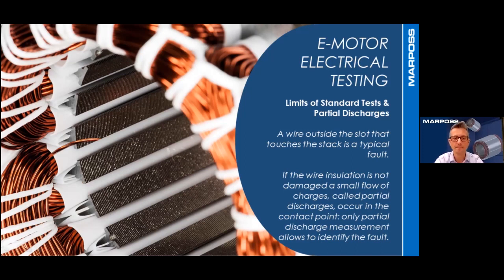In other words, the partial discharge measurement allows to detect all latent defects that could generate failure of e-motors after short operating times. This is especially true for electric motors powered by inverter, like in electric vehicles, that generate more stress to the motor windings due to the inevitable voltage overshooting.